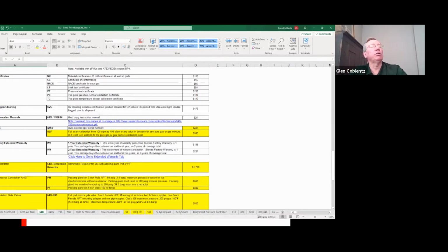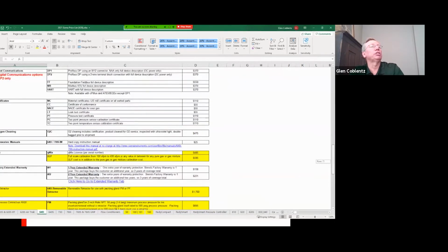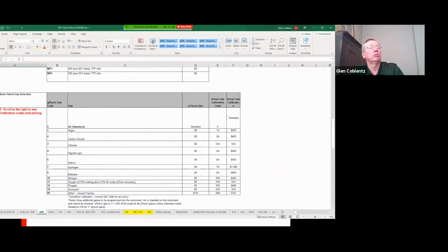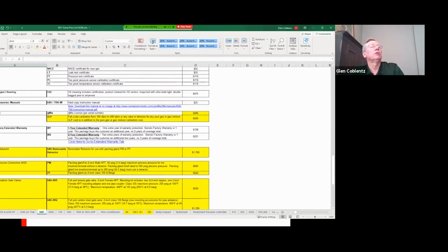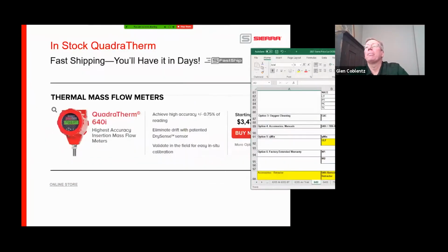Now, if you get to 0 to 500 standard feet per minute, well, guess what? You don't have to pay 585. Now you're dealing with just a regular calibration up here, okay? So 0 to 100, or 0 to 499, or any number in between, multiply by the area of the pipe in square feet to get SCFM, and then you can convert that to whatever you want. Standard cubic feet per hour, pounds, kilograms, grams, etc.